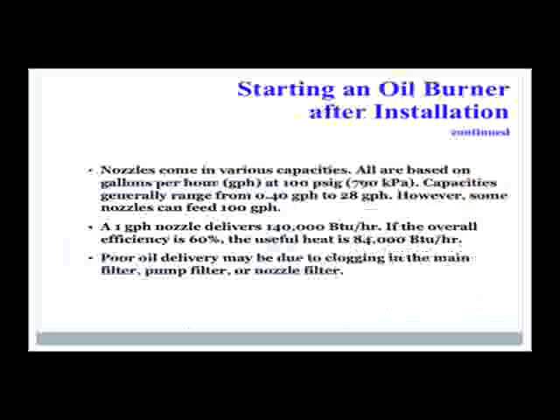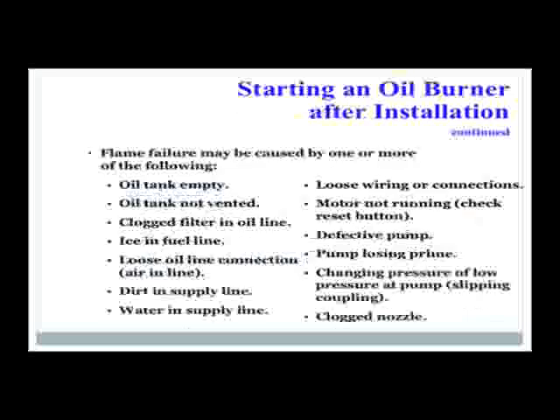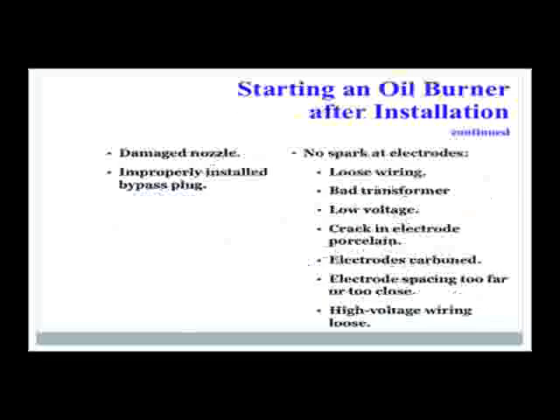Poor oil delivery may be due to clogging in the main filter, pump, or nozzle filter. Flame failure may be caused by empty oil tanks that are not vented, clogged filter and oil lines, ice in fuel lines, loose oil line connections, dirt in the supply line, water in the supply line, loose wiring connections, motors not running, a defective pump, pump losing prime, or loss of low pressure at the pump, or a clogged nozzle. Could also be caused by a damaged nozzle or improper bypass plug.